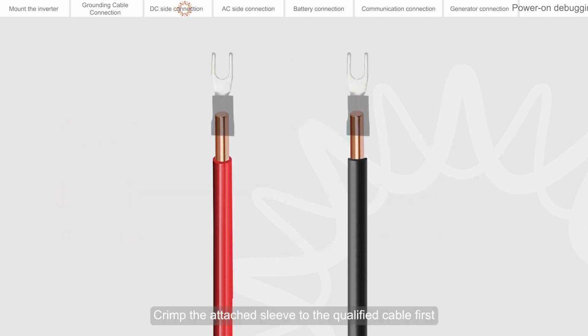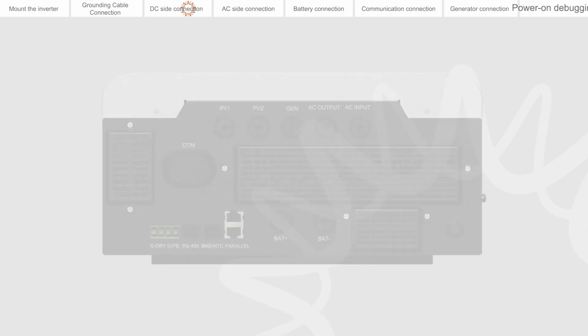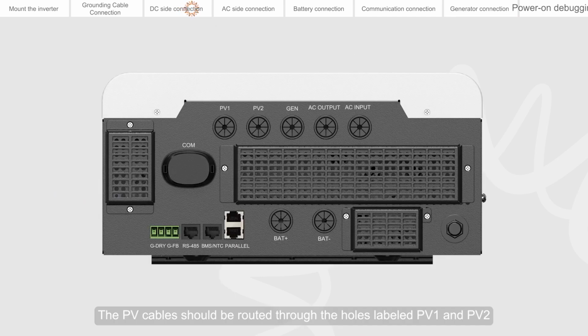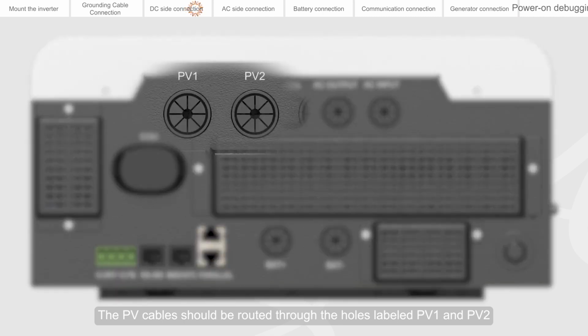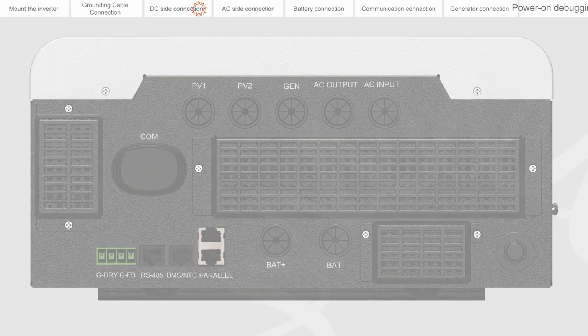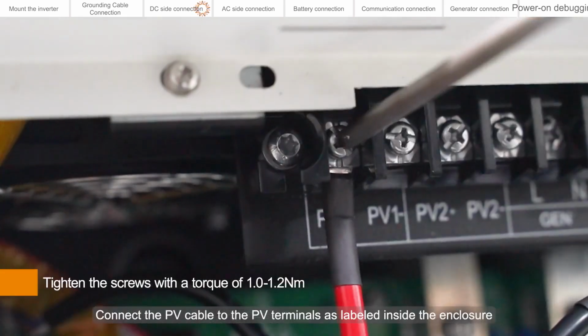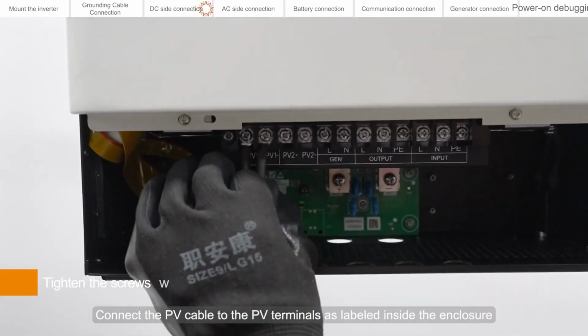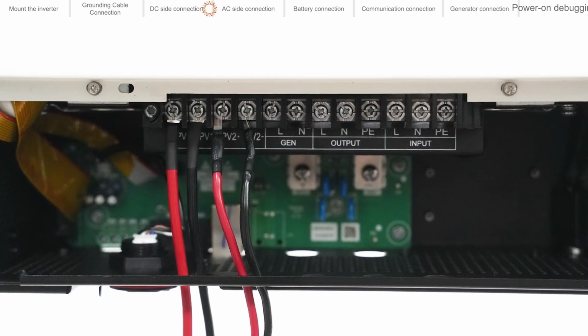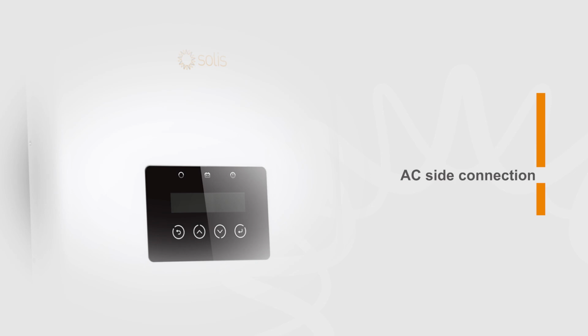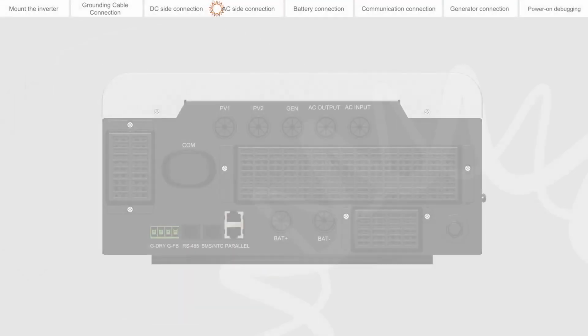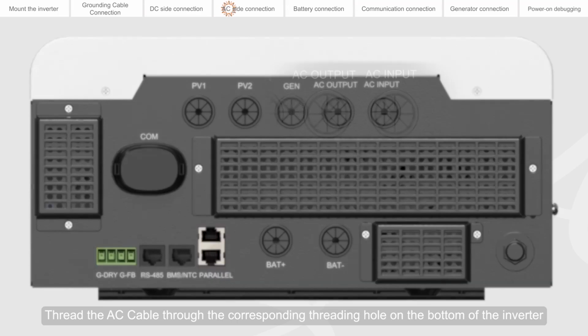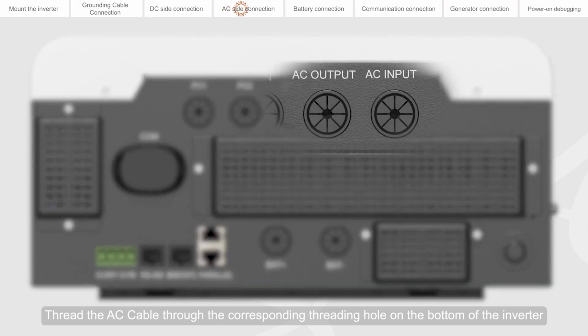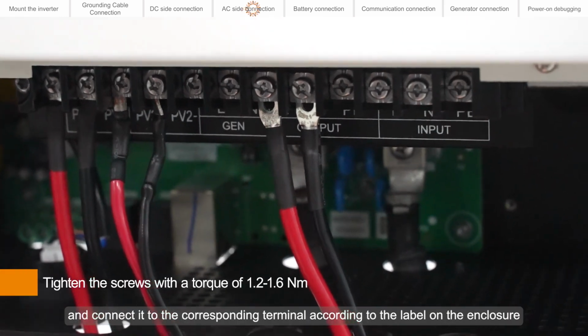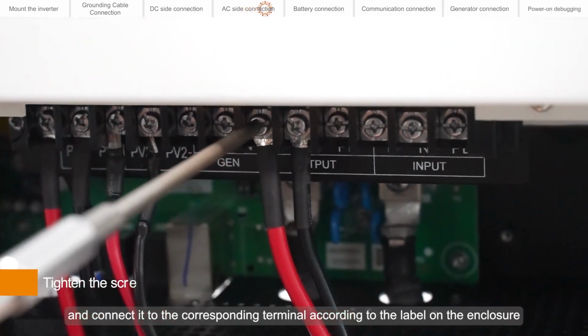Crimp the attached sleeve to the qualified cable first. The PV cables should be routed through the holes labeled PV1 and PV2 on the bottom of the inverter. Connect the PV cable to the PV terminals as labeled inside the enclosure. Thread the AC cable through the corresponding threading hole on the bottom of the inverter and connect it to the corresponding terminal according to the label on the enclosure.